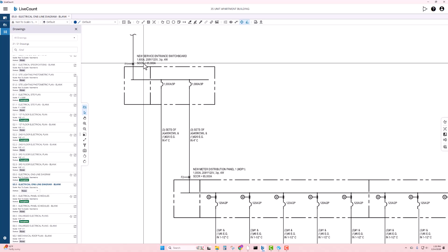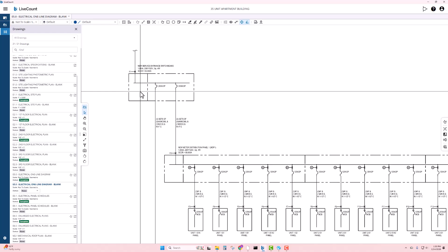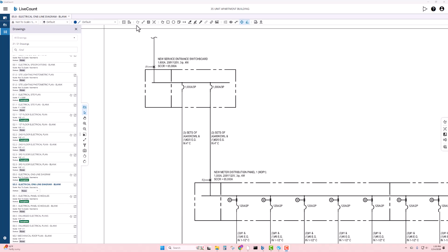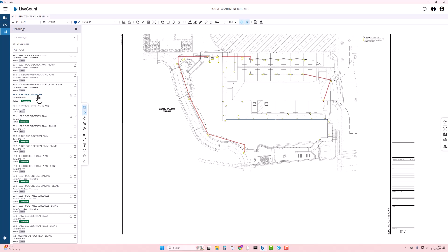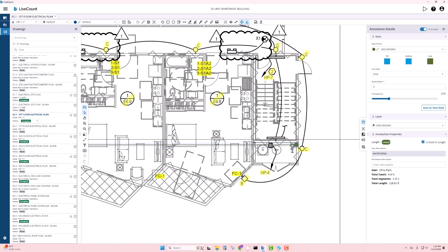Grounding, very important. A lot of times on the one line, most times they show grounding the way that you need to do it. This one, they don't show grounding. But it's definitely important not to forget grounding because it's required by code. So when you look at the grounding, we go to the first floor. Let me change this to grounding. You've got a water bond, and what you're going to want to do is look at your plumbing drawings to see where that main water line comes in. And in this case, it comes in all the way on the other side of the building. And that is going to be a 3/0 copper, and so very important you don't forget that. A little bit of money there.